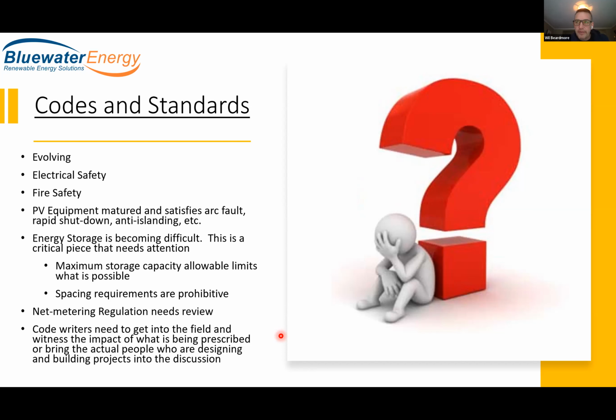Energy storage is becoming more difficult. I think this is a result of code writers, and inspectors for sure, not understanding the technology, not being comfortable with it, and then putting up roadblocks or imposing restrictions without really understanding the impact. Maximum storage capacity allowable limits what's possible. If we only have 40 kilowatt hours of total storage capacity to back up a home, that's a day maybe, if we're lucky. And if we're limited to 15 kilowatts total, in some cases we're not backing up the whole home because that's not enough power.